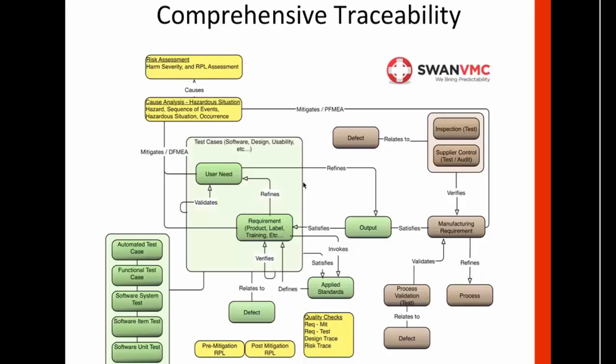But once the system's complete and the requirements checked, we need to add an additional test for the user requirement. And what we do is we bring users into the building, and then we'd ask them if the building is comfortable. So whatever that means, right? So our engineering staff has interpreted what it means with the requirements, but in the end, we need to stop, back up, and come back and check whether we actually got to the place where that user need was met.